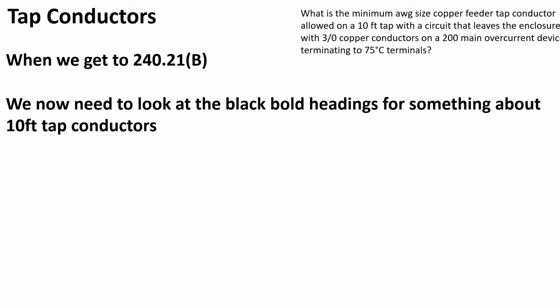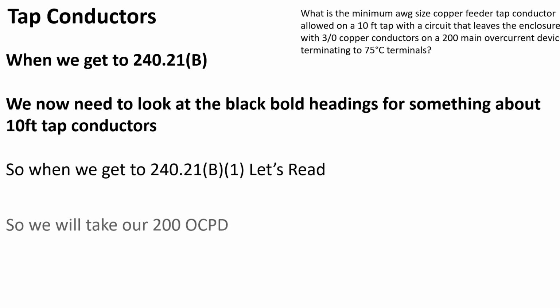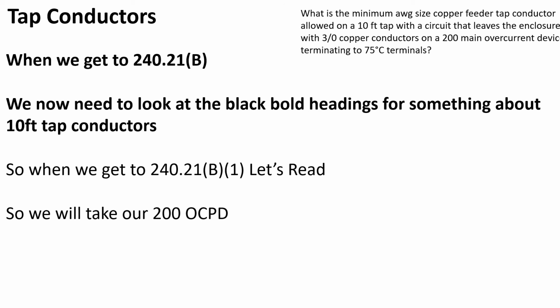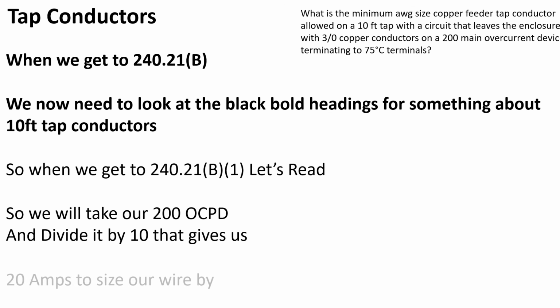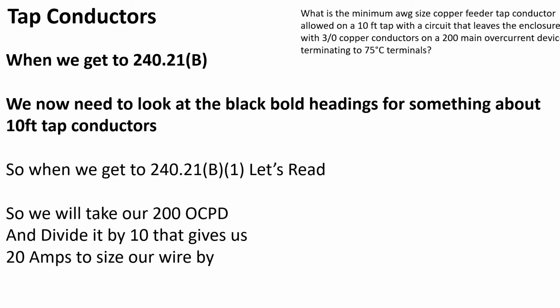So we're going to do some simple math, and this is all going to make sense, and we have one more practice question after this. Okay, so we're going to take our main overcurrent protective device, and we need to divide that by 10, because we have to do at least 1/10 of it. So we're going to divide by 10. That's going to give us 10 equal portions of the 200 amps. So in this case, 20 amps is what we now can size our wire by, minimum. So even if you only have a 3 amp load and you know the load, you must use a minimum of 20 amps, and that's what you must size your wire by.